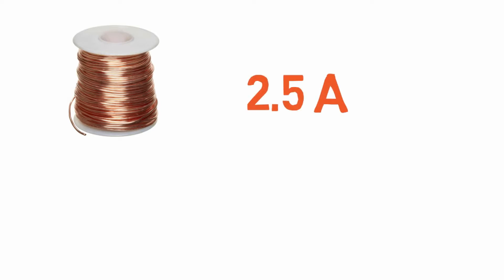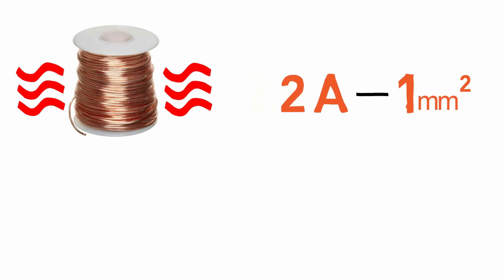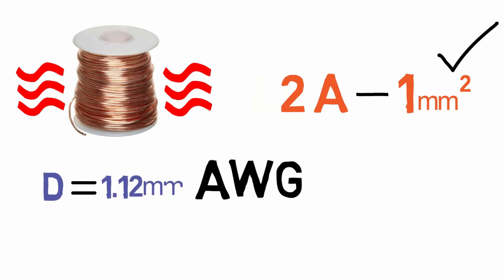Generally for 2.5 amperes of current, 1 mm square cross-sectional area of the wire is sufficient. For more, heat will dissipate and heating losses will increase. According to our design, 2 amperes is the load current, hence the wire having 1 mm cross-sectional area will be sufficient for us. For more details you can see the American Wire Gauge chart, that is AWG chart for reference.